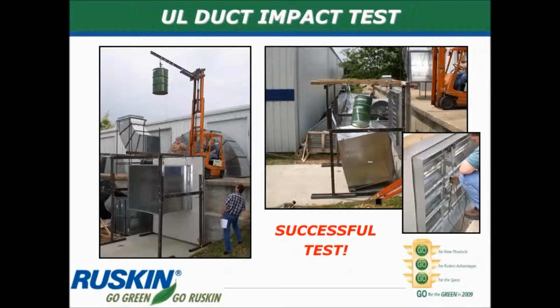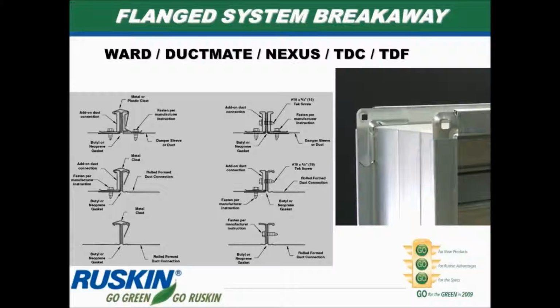And then after the test is done, that's only the first half of the test, then they have to inspect the damper and make sure that it still is within the plane of the wall and that it operates. They have to cycle it to make sure it does close. So it's a very, very tough test to make sure that that damper and sleeve assembly stays in place in the wall and the ductwork connected to it breaks away and doesn't yank it out of the wall.